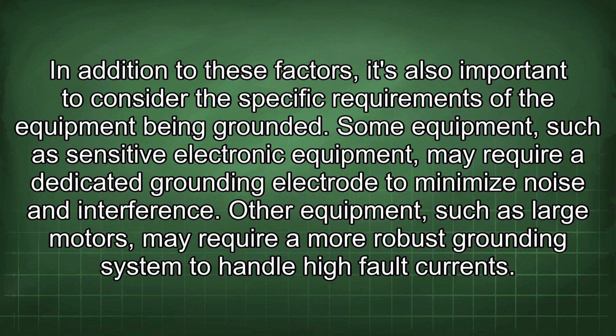In addition to these factors, it's also important to consider the specific requirements of the equipment being grounded. Some equipment, such as sensitive electronic equipment, may require a dedicated grounding electrode to minimize noise and interference. Other equipment, such as large motors, may require a more robust grounding system to handle high fault currents.